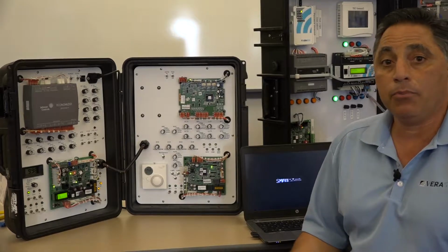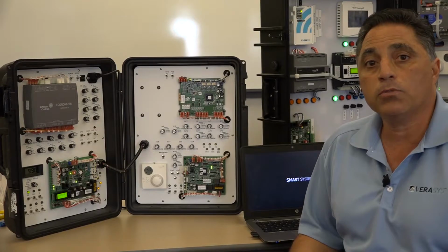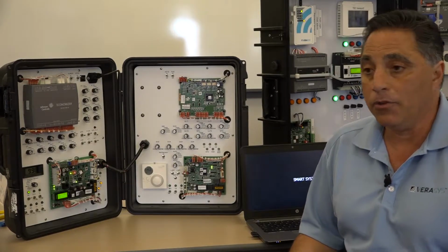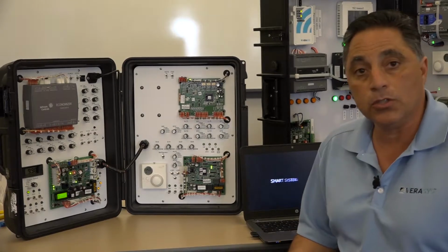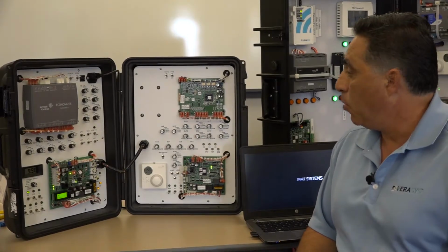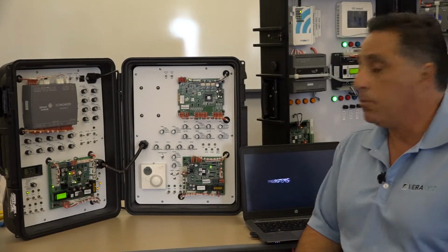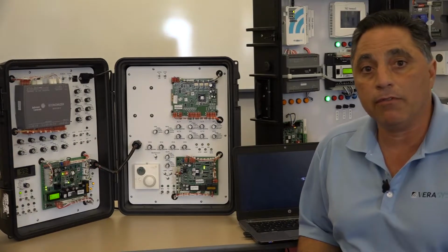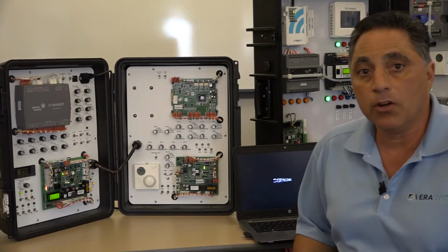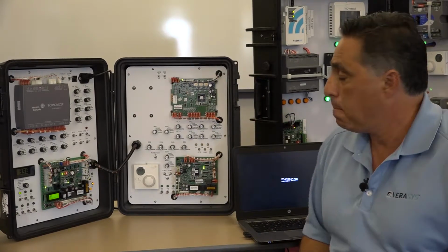The FDD, being part of the refrigeration, obviously only runs during the warm time of the season. Now, if you live in the southern part of the country or western part of the country and there's always warm weather there, most likely your FDD is running all the time. If the temperature dips below a certain temperature range, most likely around 55 degrees, then the cooling is not going to be activated, and your FDD is really not running.